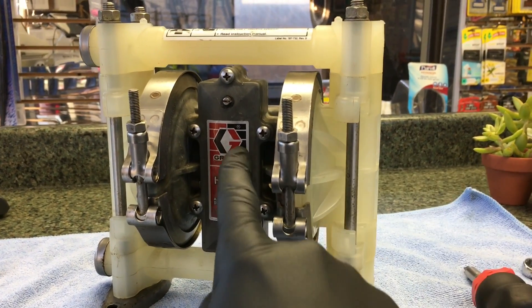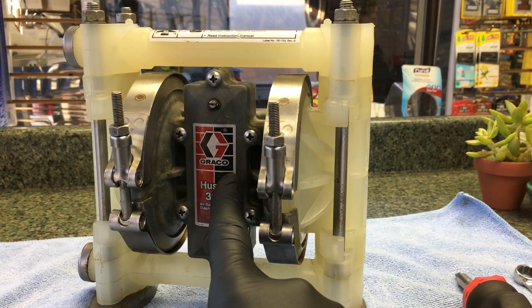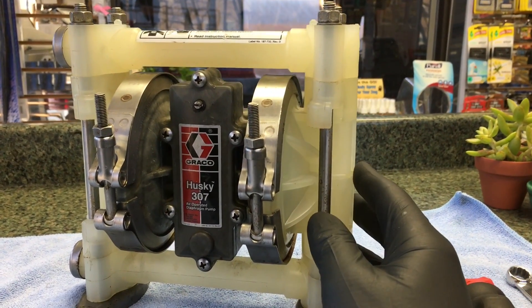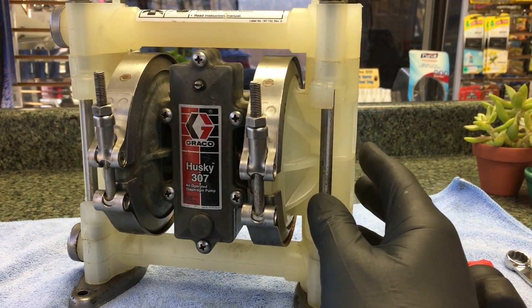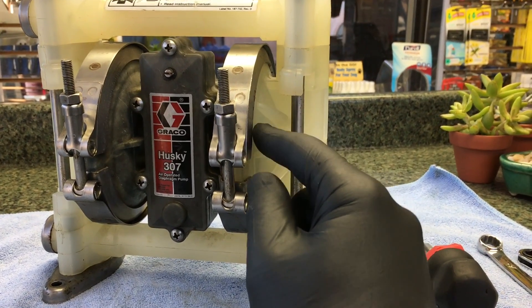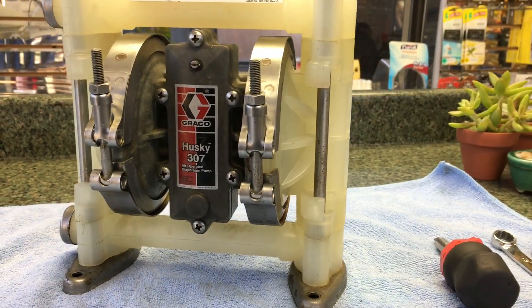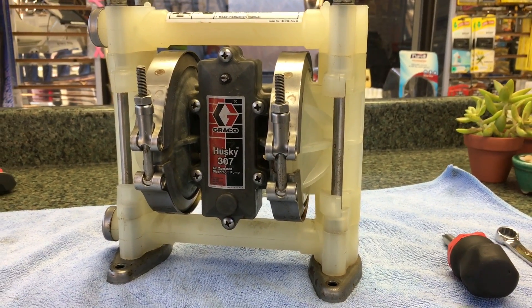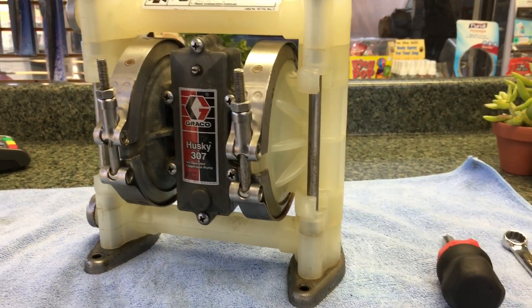But many other times - this is a car wash, I have had these used in the past - most of the time it's the diaphragms inside. Either they get a tear or, depending on what kind of chemical you're using, they just wear out over time.